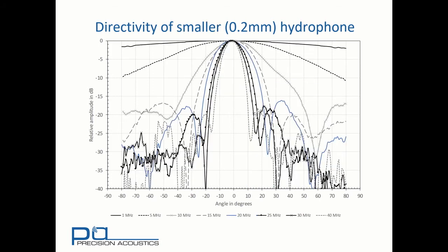In contrast, we'll consider a 0.2 mm needle hydrophone. Here we can see that even at 5 MHz, the fall off from the normal incidence amplitude is only 10 dB at plus or minus 80 degrees. And even the 40 MHz response is broader than the 10 MHz response for the 2 mm needle hydrophone.